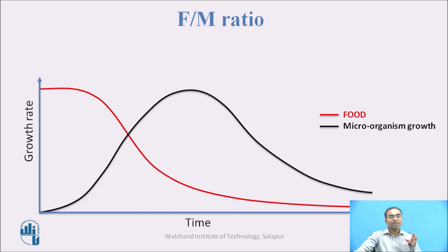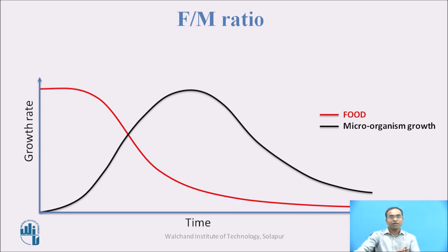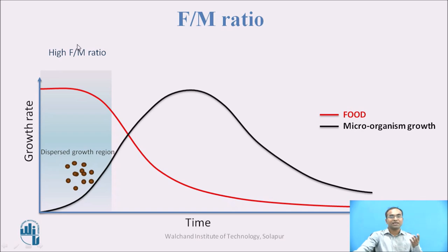In the earlier session we studied the declination of food in the tank, the increase of microorganisms to the peak, and then declination going towards the regeneration process of microorganisms. In this growth phase, the food to microorganisms ratio is most important. If we put a higher F by M ratio, it means food is present in much higher quantity than the microorganisms. At that time dispersed growth will form — very few microorganisms will develop — so this stage will not give us proper activated microorganisms.